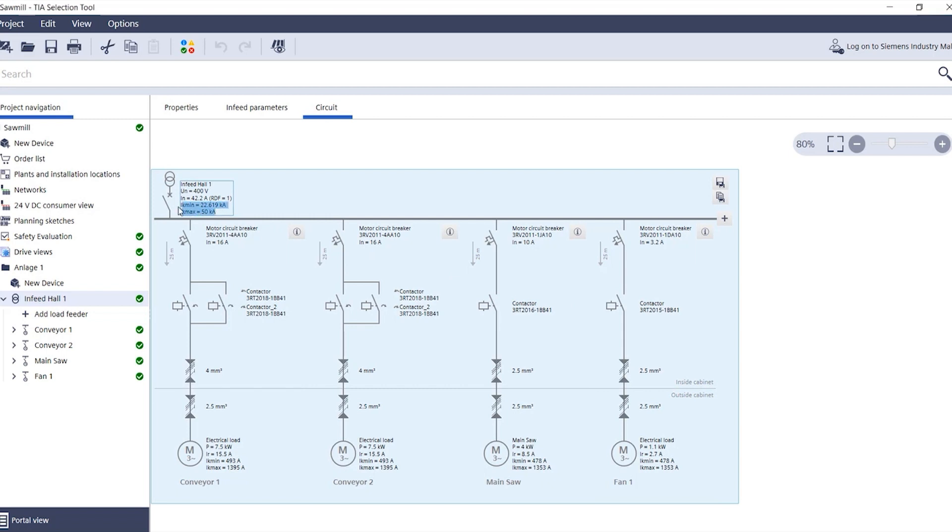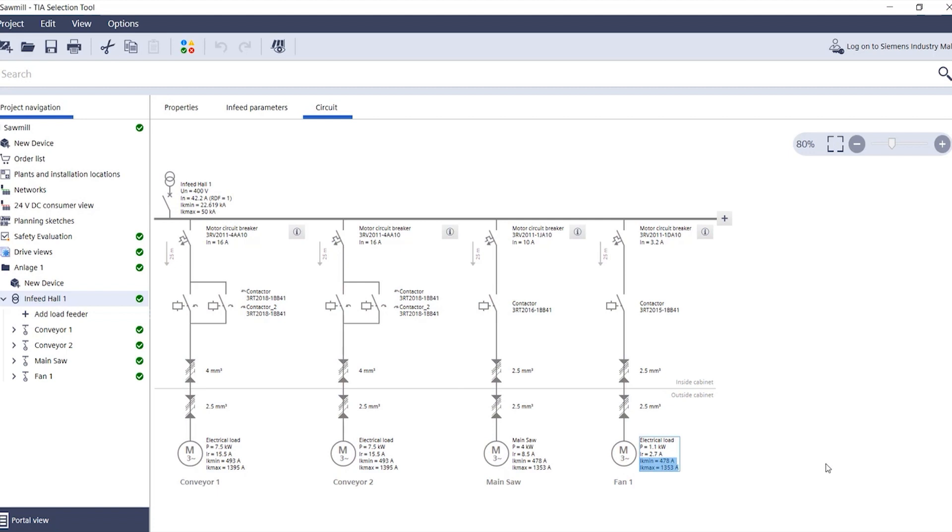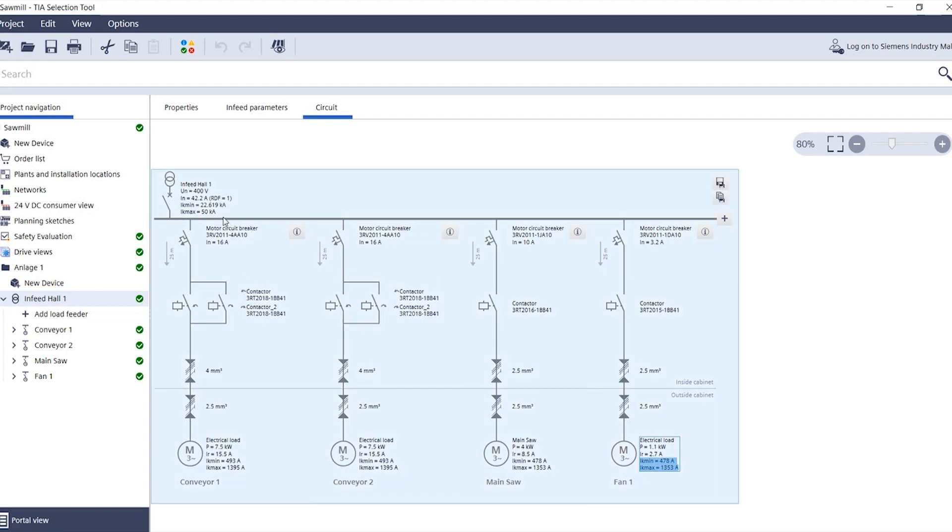Here in the overview you see the short circuit currents on the one hand up here at the infeed and on the other hand down here directly at each individual load. These are the calculated short circuit values.